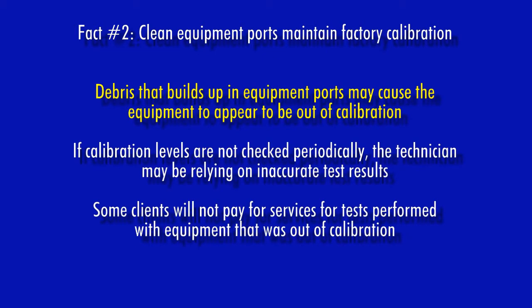Fact number 2. Clean equipment ports provide assurance that equipment factory calibration levels are maintained. If debris is allowed to build up in equipment optical ports, the equipment will appear to be out of calibration and may cause an unnecessary trip to the calibration facility. Worse yet, if calibration levels are not checked regularly, the tester could be producing inaccurate test results and the technician may not even know it. In addition, some customers will not pay for services if the test equipment was found to be out of calibration.